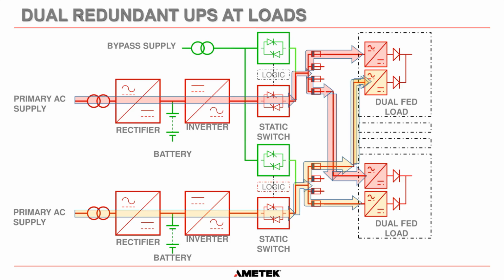This is another design of system that we've seen gaining traction. I see some engineers speccing this out for new UPSs, and it's when the UPSs are connected with redundancy at the loads themselves. Okay, so what you have is two individual UPSs. Okay, let's say this is A at the bottom and this is B at the top. And you can see, let's draw this one out here. So B goes up into this power supply here, and A goes up through a distribution board into this power supply here.